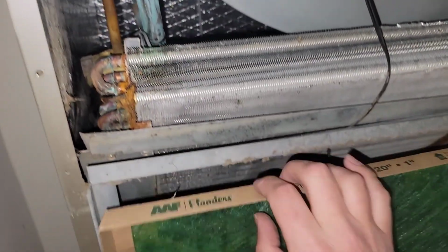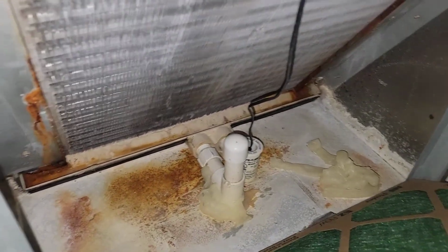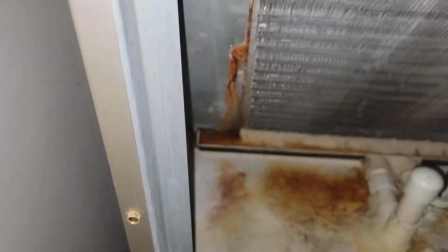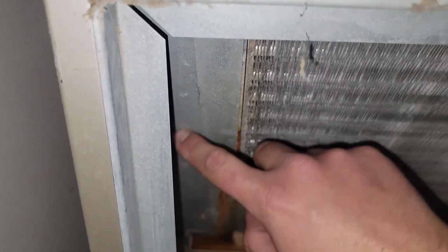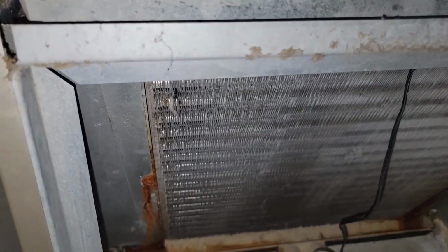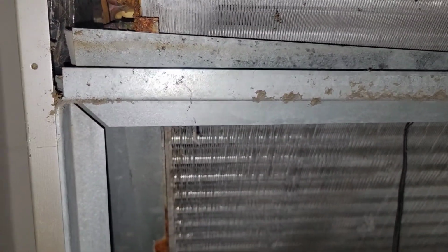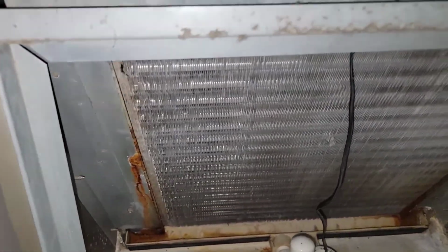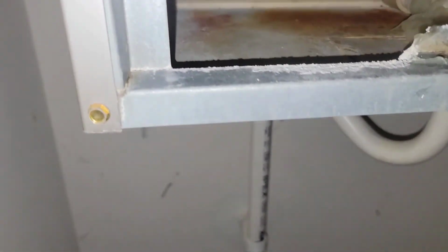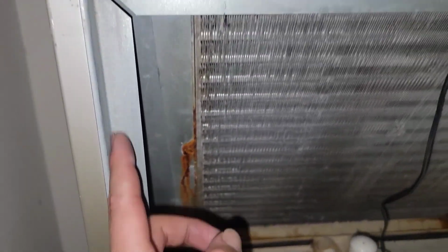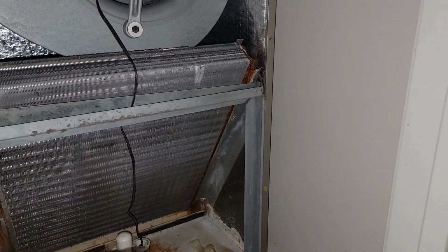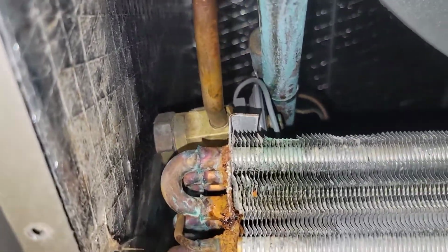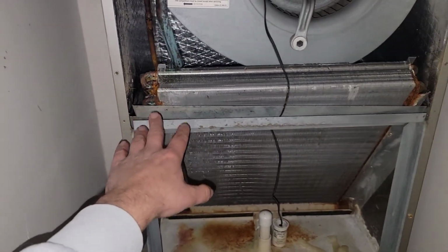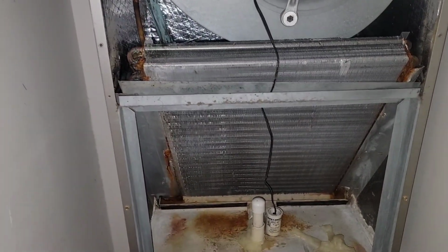The best way to change this is there are some screws you can take out. And they are here and here or right here. And then you can take this coil, you can take this bracket off too. There's a bracket. Hold on, let me show you real quick. So there's part of the bracket right here. You can take this whole entire bracket out and you can move this coil down so you have more room to replace this TXV. Some would think you can't replace that TXV. You can. I did one last week.